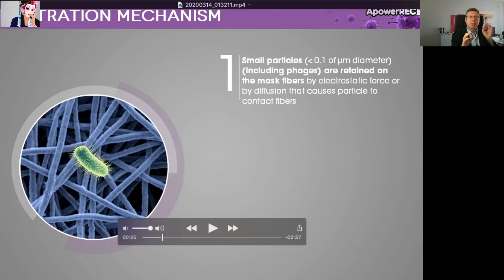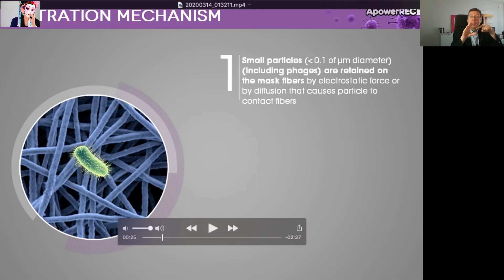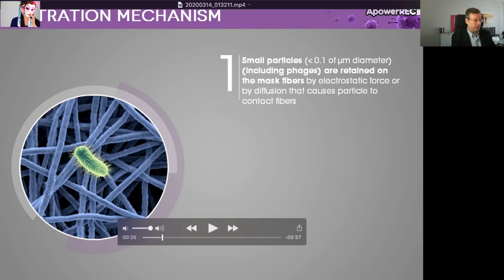Also, very small particles are doing what are called Brownian moves, which is random moves in the air. As they are passing through, although they are going to go through the empty space of the media, due to these random moves they will hit the filter fibers and they will be filtered out. So very small particles will be filtered out by these two filtration mechanisms.